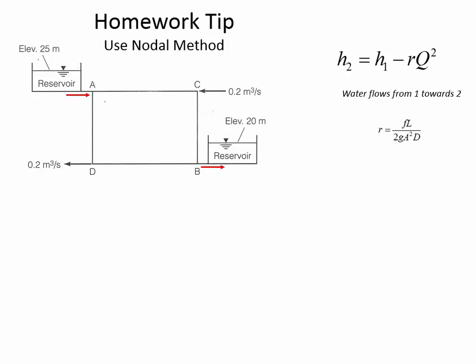You're going to start by making the fully turbulent flow assumption. You'll know the pipe diameter and the relative roughness — variable k sub s or epsilon, they're interchangeable, different texts use different variables. One of your starting points will be to calculate an R for the pipe, where R is a function of its length, diameter, and F value. Not only are you going to have to guess the F value, you're going to have to guess what direction the flow is going. You focus on just one junction at a time.